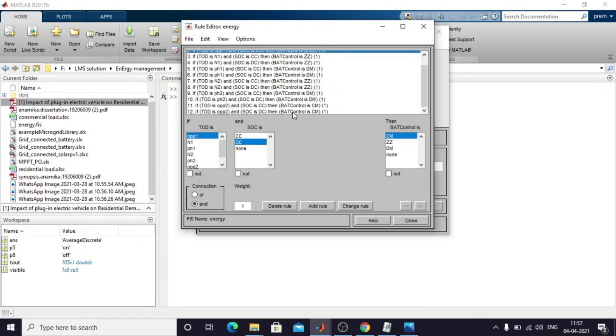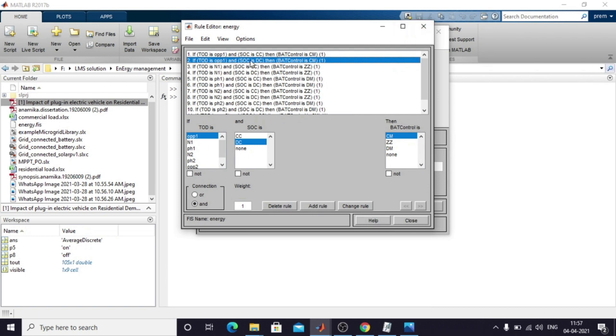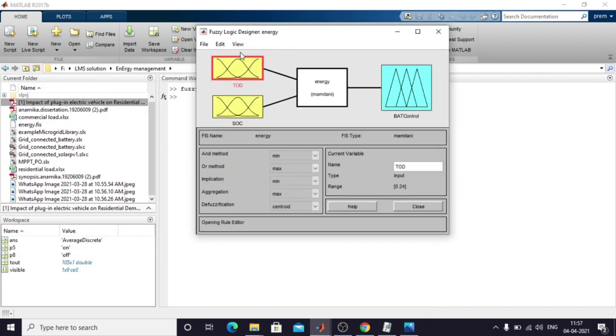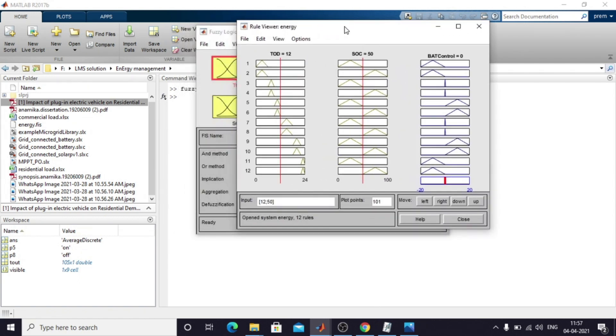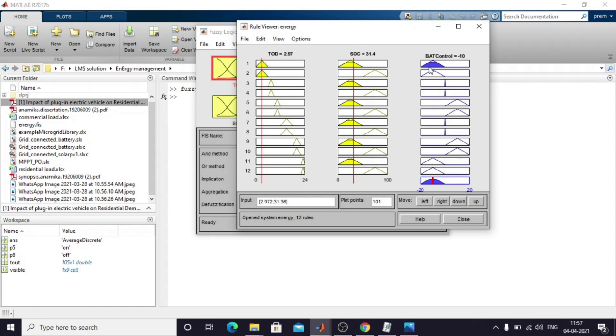Here I can explain with a picture. You can see that when the SOC level is 50 and the time of day is 12, the battery control receives zero — meaning the battery is in normal condition. For example, from 0 to 6, when the SOC level is 31.4 and the time of day is 2.9, the battery receives a negative power input — meaning the battery goes into charging mode.